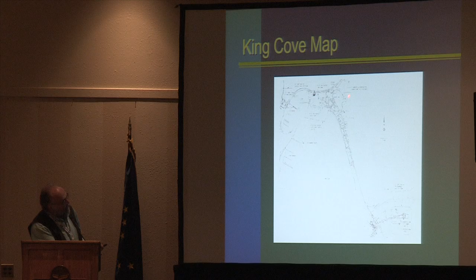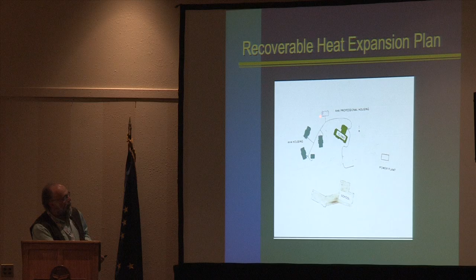This is a better photo. This is the diesel plant we looked at. From the diesel plant over here to the school, that was phase 1, a couple football fields in length. Phase 2, the report I just showed you, was to take the system up to the new King Cove Clinic, and at that point it was going to stop right there. But when Steve and others realized maybe we've got more recoverable heat available than we thought, we talked very nicely to AEA, and they said, alright, maybe we can add this unit, and we can add these units. So in the end, phase 2 was not just more power to the King Cove School, but more recoverable heat to the clinic and to basically 11 living units.